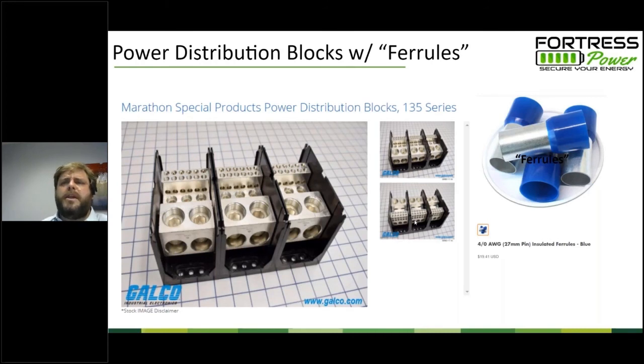But the one component that I don't see a lot of installers using that I think they need to be more aware of is this component that is called a power distribution block. And it is designed to go inside a wide gutter or a metal termination block. And like the bus bars, they have these insulated fittings that can get mounted into the box. And then, you'll get a listed terminal. Sometimes for parallel wiring, you can have your smaller battery cables come in one side and your larger combined battery cable come out the other side. We have one for our positive side, one for our negative side.